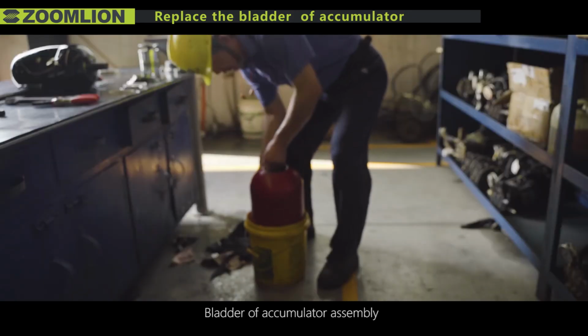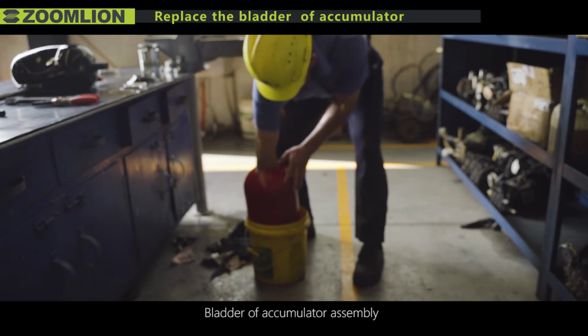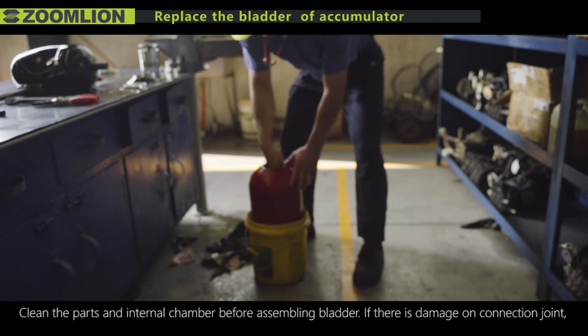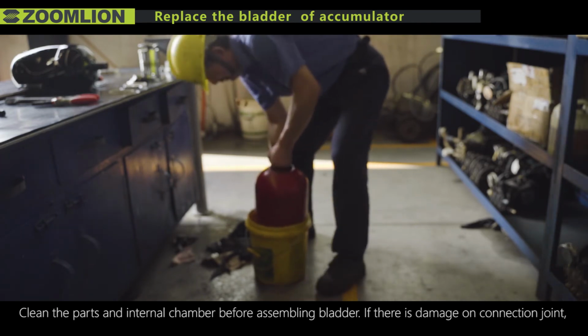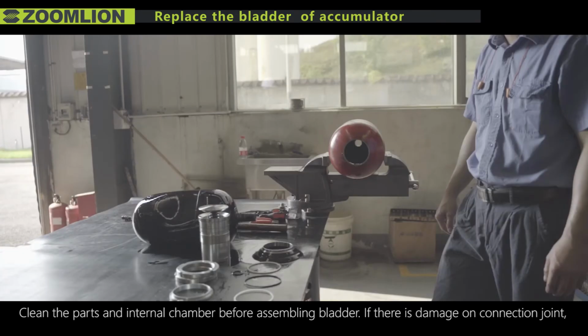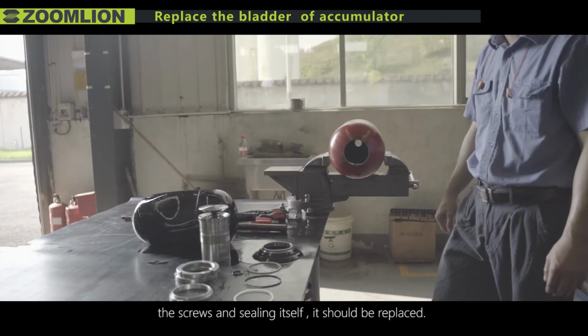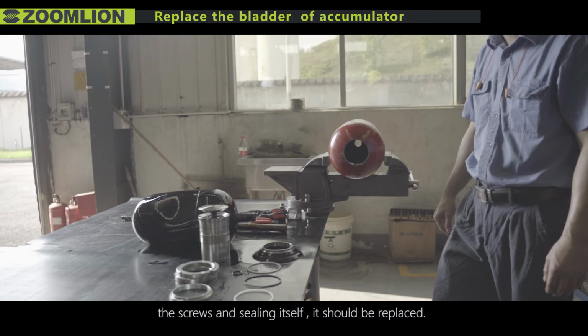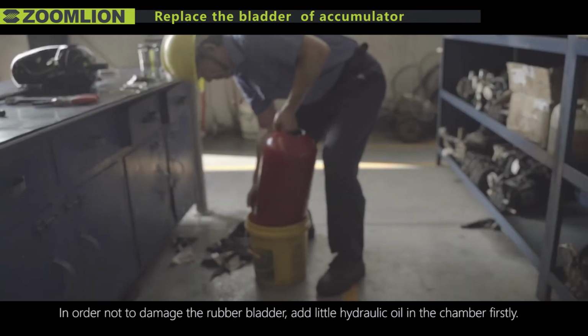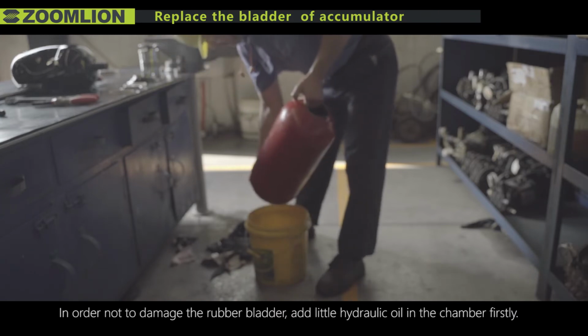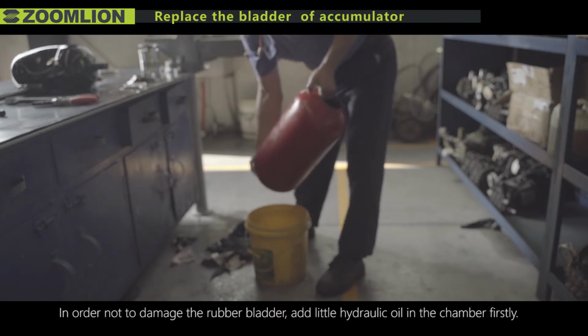4th, bladder of accumulator assembly. Clean the parts and internal chamber before assembling bladder. If there's a damage on connection joint, the screws and sealing itself, it should be replaced. In order not to damage the rubber bladder, add little hydraulic oil in the chamber firstly.